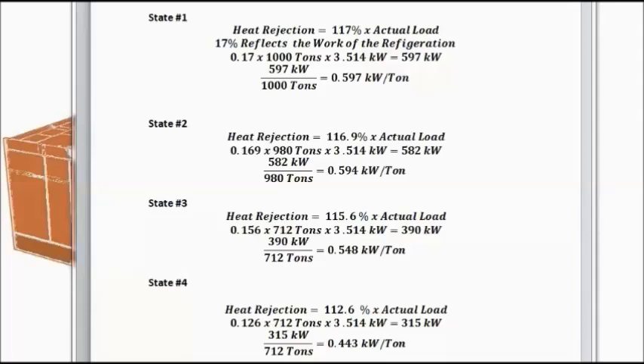The heat load in excess of the actual load represents the work input by the chiller compressor. So, with negligible exceptions, this accounts for all of the energy input. And we can then calculate the chiller design power and calculate its design efficiency. In state 1, the chiller efficiency is about 0.597 kW per ton.